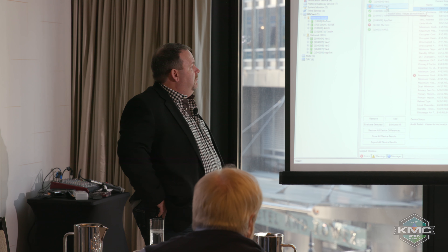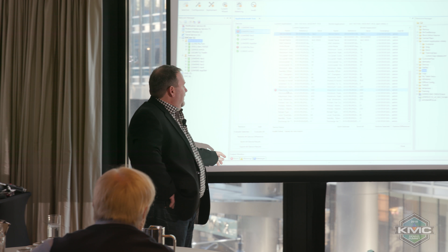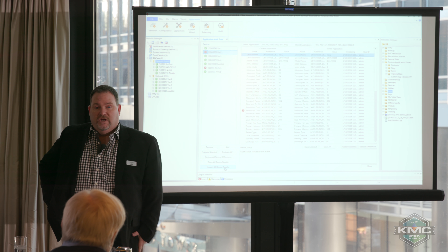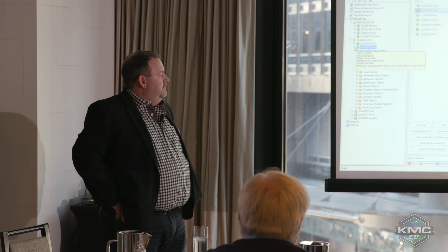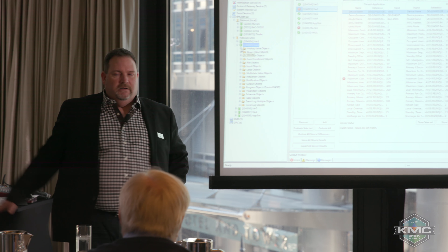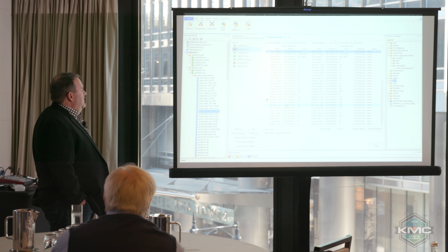Has anybody ever heard all this? So you go back to the job and say, okay Mr. Customer, I'm going to run the audit on here and it's going to tell me everything you've changed in the last six months on your properties. You can even export that file out and say look, all this stuff was changed. All you have to do is put it back the way it was - hit restore - and it'll be just like it was when you left the job site. All your setpoints and everything will go right back the way they were. Here's your service report. Hopefully. Very powerful tool, very handy to use.